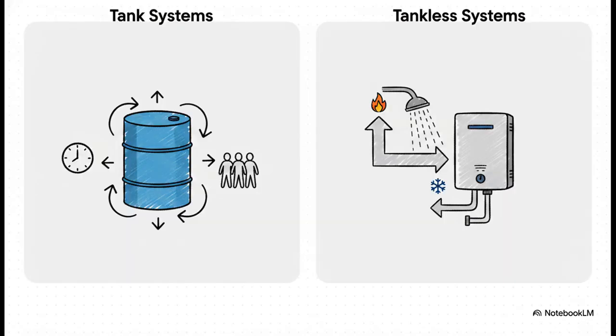Now, sizing these things operates on fundamentally different physics today. For tank-based systems, your critical metric is the first hour rating, or FHR. A typical 4-person home usually needs an FHR of around 65 to 80 gallons. But if you look at the tankless side, it's a completely different ballgame. It relies strictly on flow rate, gallons per minute, and the required temperature rise, which engineers call delta T. To put that into perspective, if your incoming winter groundwater is a freezing 50 degrees and you want a 120-degree shower, your system has to achieve a delta T of 70 degrees. That massive temperature lift will significantly cut the actual gallons per minute a tankless system can push out, which is absolutely crucial to know before you buy.